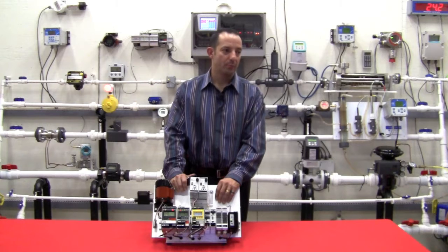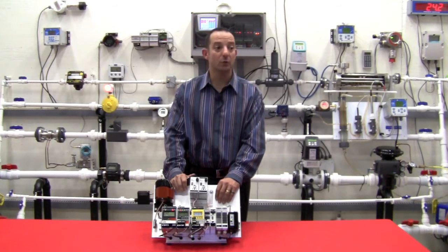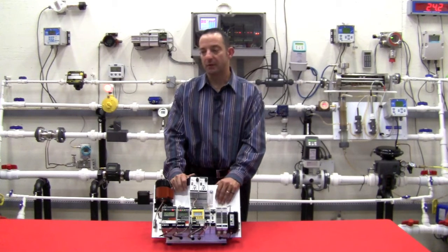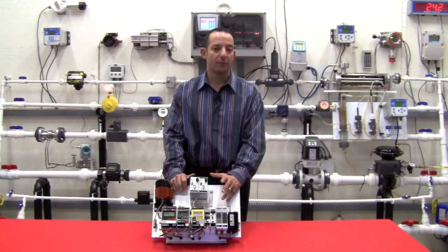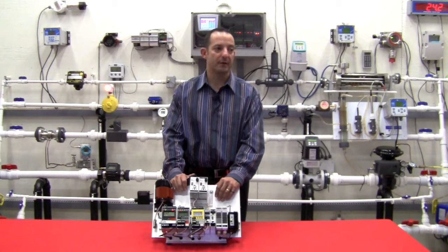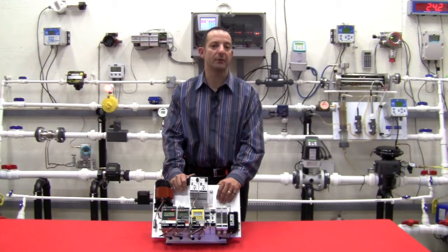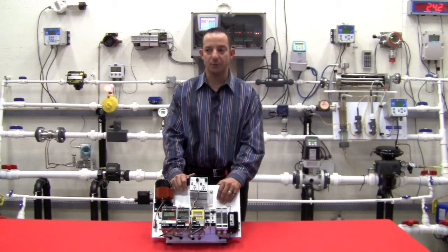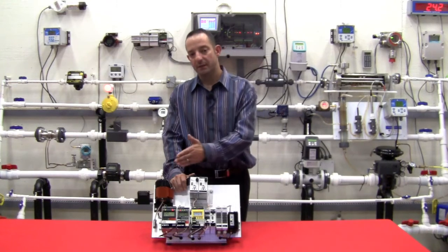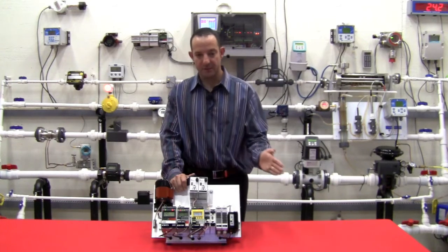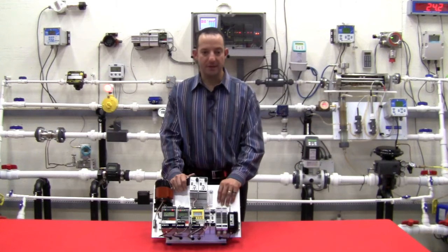Again, you can mount these out in the field in an unheated or uncooled enclosure, in the case of an environment that's going to get cold in the wintertime, or for example, on the burner deck of a power plant where the temperature can routinely get up to 130, 140, 150 degrees. You don't need to worry about its effect on the reliability of the alarm trip or any drift on the input circuit. When we specify our input accuracy, that's over that entire temperature range.